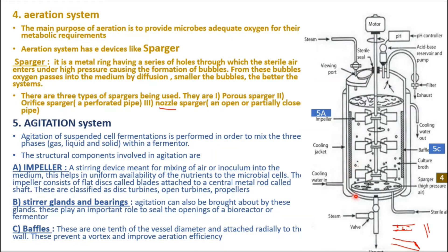The second component is seals and glands on the bearings, present at the openings of the bioreactor. The third component is baffles. Baffles are about one-tenth of the total vessel diameter and are attached radially to the wall. Their main function is to prevent vortex formation and improve aeration efficiency.